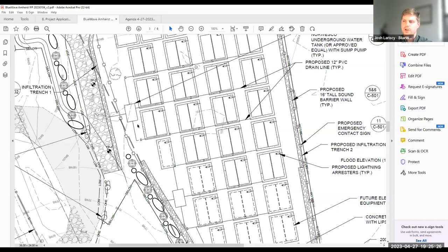Yes, we would look to install some kind of monitor or alarm to know the status of the sump pumps. We'll tie the monitoring systems to the pumps, because we want the pumps to shut off if there's a fire alarm or any condition triggered within the enclosures, as a fail safe. So we'll tie that in, and there will be monitoring on those pumps.